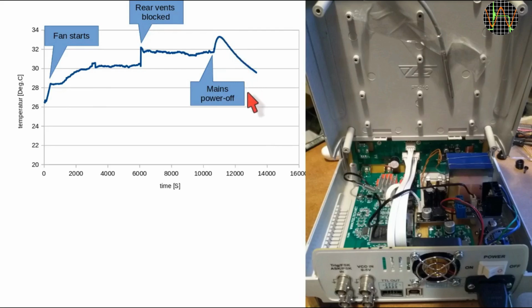You can avoid this heat build-up if you turn the unit off in 2 steps. First, press the power button on the front, which just puts the generator in some kind of standby mode but leaves the power supply and fan going. Then, after a few minutes, turn the power off at the back too.